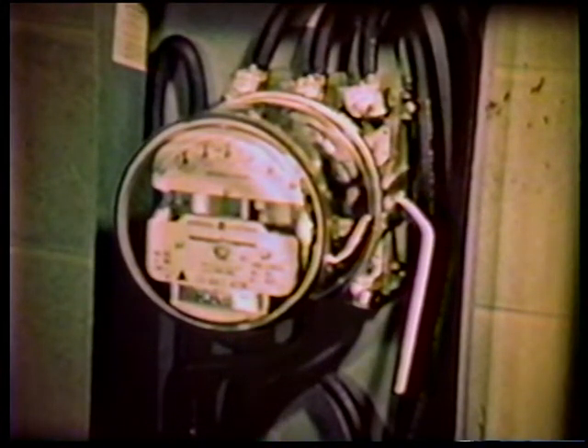The bypass switch should never be operated without a meter or jumpers in the socket. These switches are not designed to pick up or break a load, as you can see. On older installations where test blocks or socket wrench-operated bypasses are used, special care and insulated tools are necessary to bypass the load safely. Where no load bypass means are available, you will have to use the customer's main switch to disconnect any heavy loads flowing through the meter.